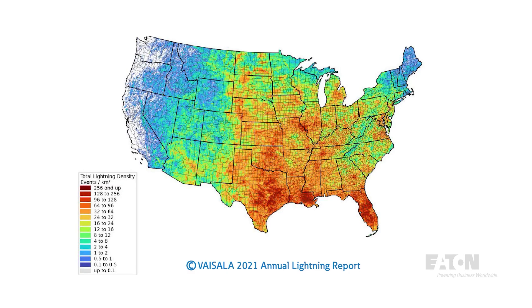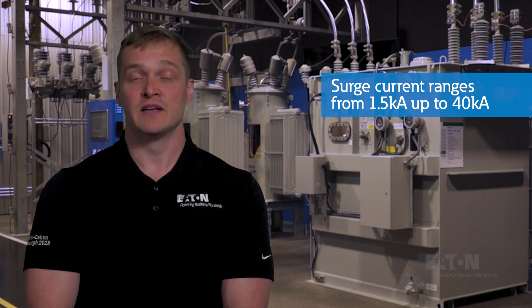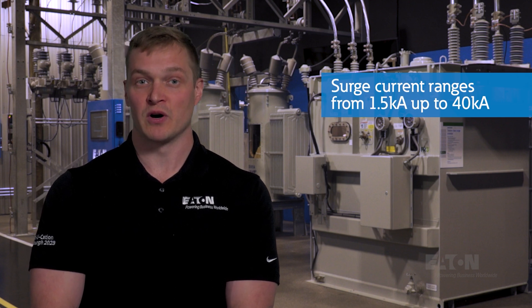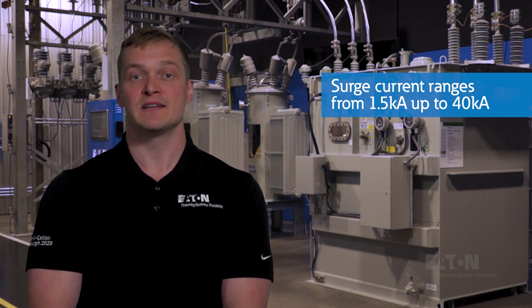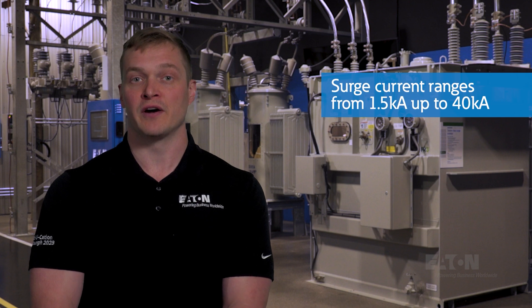The geographical location is also important when sizing an arrestor, due to different lightning patterns. Many organizations publish annual lightning maps that detail intensity and frequency of lightning on a regional basis, so engineers can estimate the total surge current present on a system in a given area. The range of surge current ratings goes from 1.5 kA up to 40 kA, so engineers have to make a judgment call. They need to look at the intensity of lightning in their area and decide what surge current is reasonable.